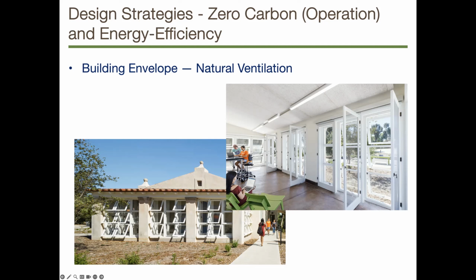What they decided to do with the skylights was make them operable, creating a path for air to move through the crawl spaces underneath the classrooms and up through the skylights, naturally drafted. They didn't use a fan, except very slow-moving ones for days with no air movement outside at all. This way they got ventilation and air movement, and used it at night to pre-cool the structure as much as possible.